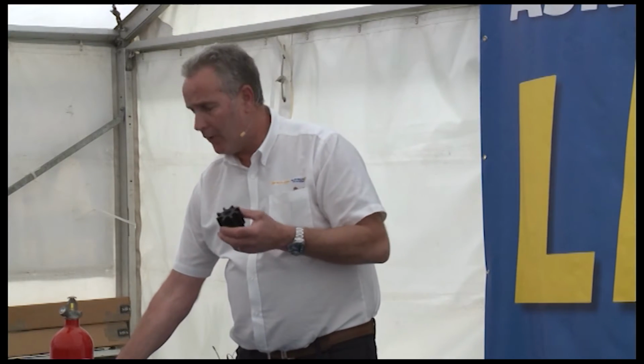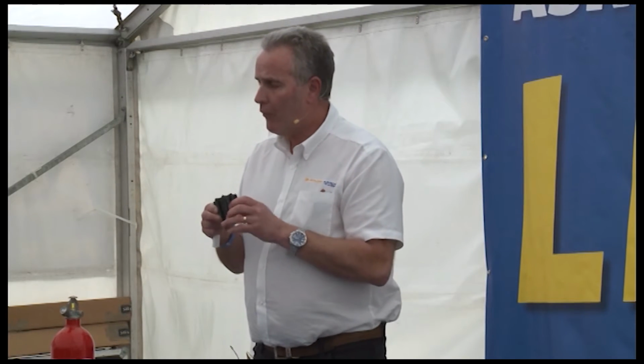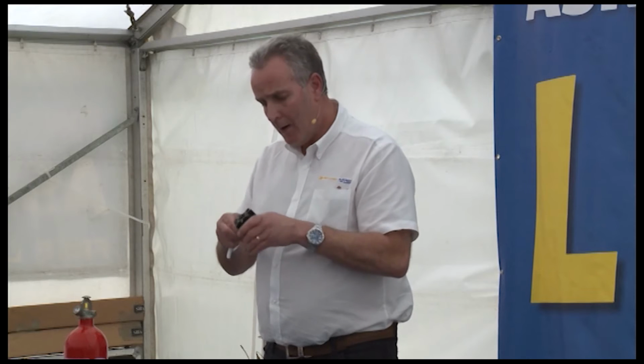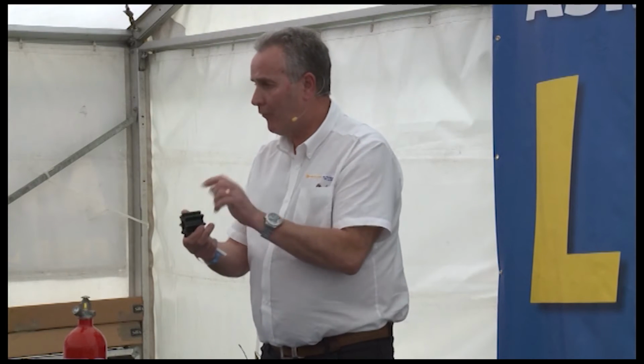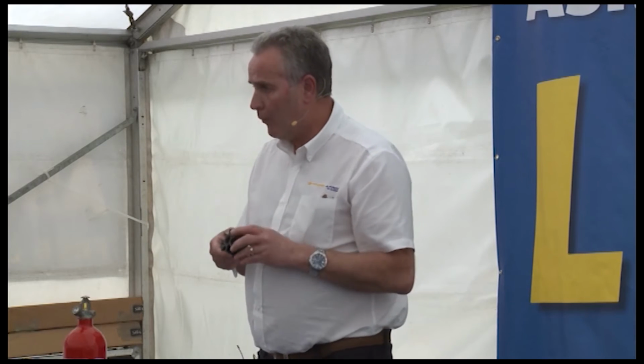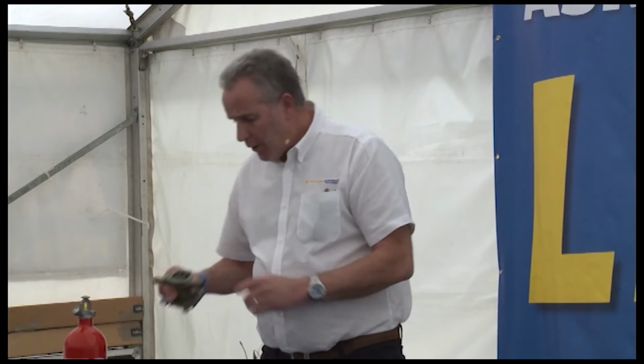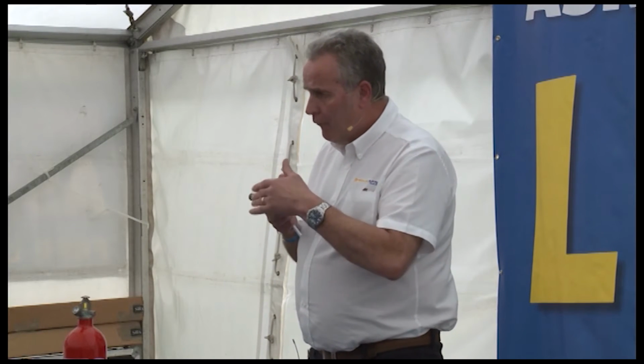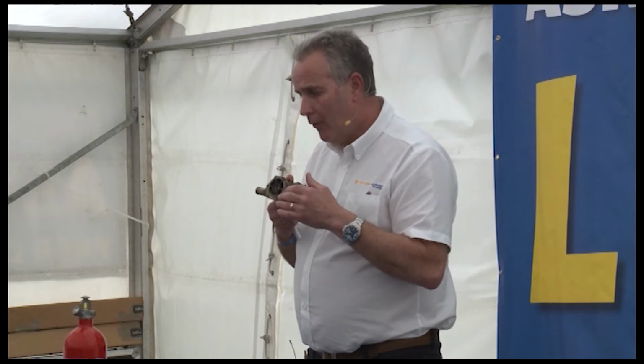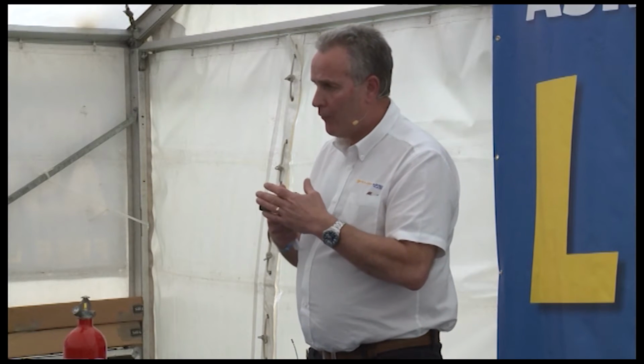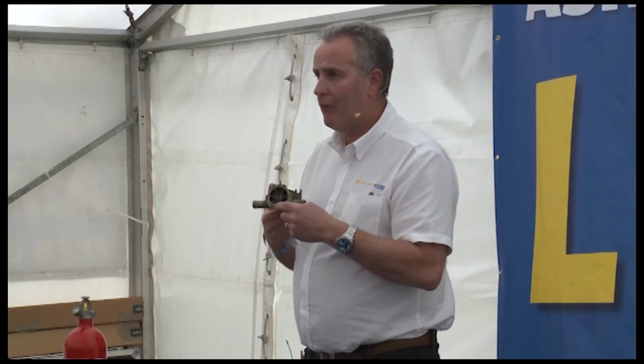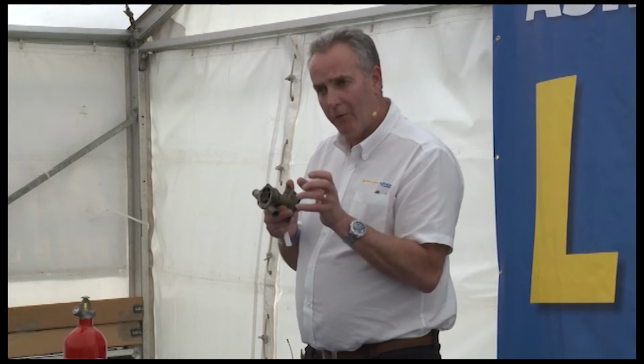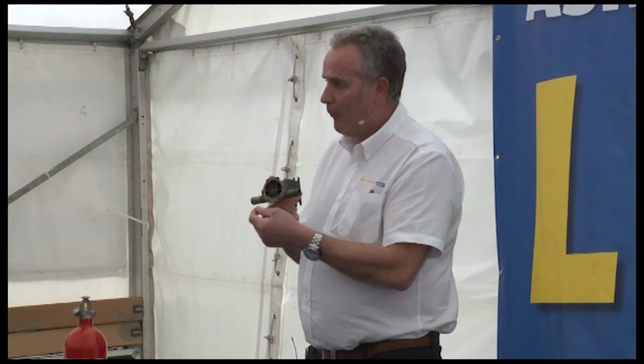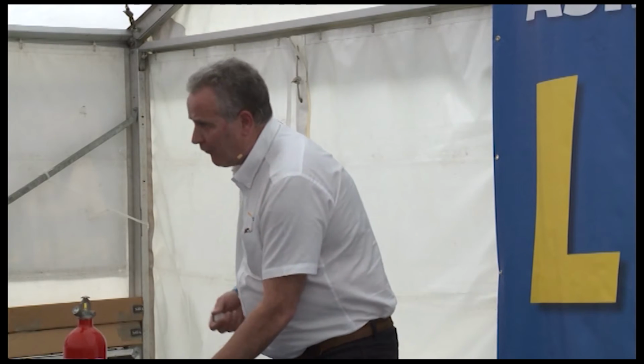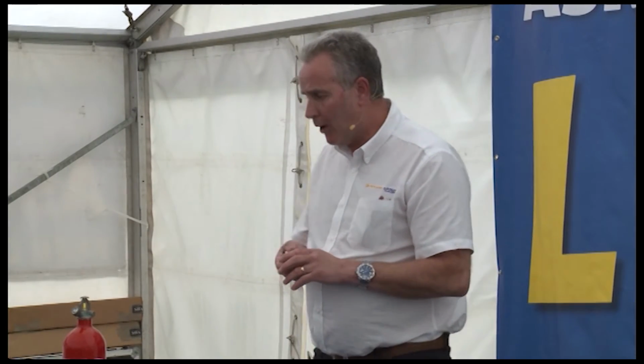If your hand's a little bit weak, and you've got a slightly larger impeller, the tip is to put a cable tie around it, which will close all the fins up one way, and then you'll find it easier to tap it into the housing, and then the clip itself will just fall off. But when you put that cover plate back on, if you have a smaller one that has a paper gasket, make sure that surface is clean, the back plate is clean, and then you put that gasket on dry. You do not put grease on it, because if you put grease on that gasket and do it up, it would just splay the gasket and thin the gasket out. And quite often you find there's a great big lip of paper, and sometimes that may leak. So that's just a little tip to keep an eye on.